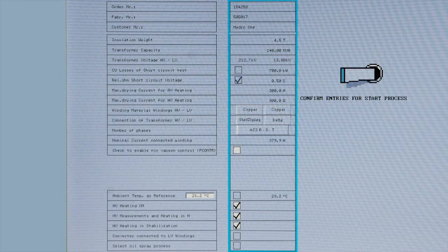Maximum drying current for the high voltage heating is the absolutely maximum current that will not be exceeded by the LFH plant, even if the CF factor is asking for more current. It is used as a design safety factor to prevent damage to the transformer. The value is entered as amperes. Material composition for high and low voltage windings is important to know in order to calculate the resistance and temperature relationships. Either copper or aluminum is possible, and they can be different in the high voltage and low voltage windings.